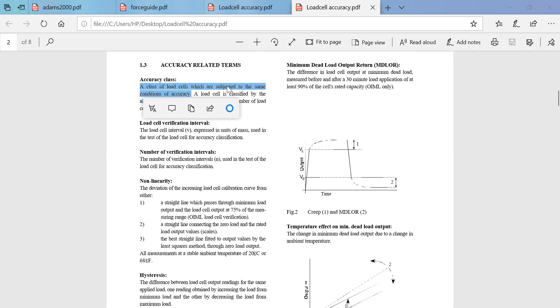So that will be classified as a specific class. Similarly, there could be other load cells whose accuracy is a little lesser than 100% or 99.9%. Suppose they lie between 90 and 99.99. Those will be classified into the second class. Similarly, others might show an accuracy of 85 to 90%, so they could be put into a different class, right? The accuracy is also affected by the parameters I told you here: how it is characterized, how it varies linearly, its temperature effect, its hysteresis effect. All those things indirectly affect the accuracy level of the load cell which has to be classified. So based on this, the class of accuracy will be classified. Once the accuracy class is classified, only then will it be helpful for you to grade a given load cell. So you should be aware of this terminology.